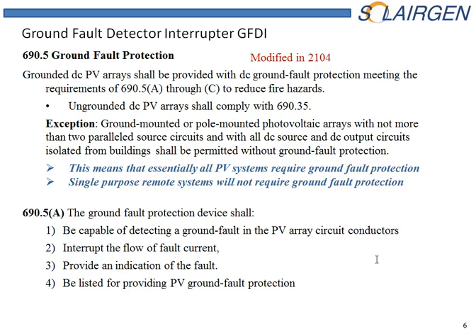Ground fault detection. This is required on PV systems, so is arc fault protection. The label should be on the inverter, both the arc fault and the ground fault label, if it has it in the inverter itself, and I'm sure that it will. So verify that. If it doesn't, then you'll have to put that on yourself.